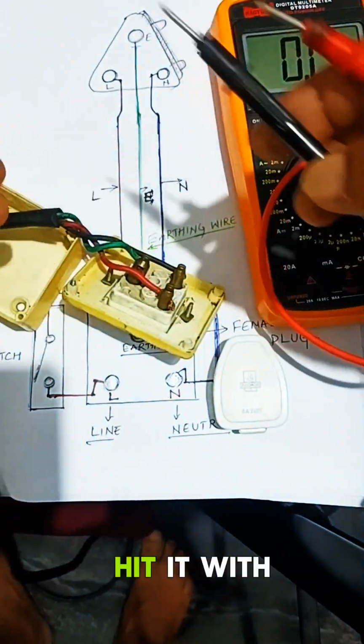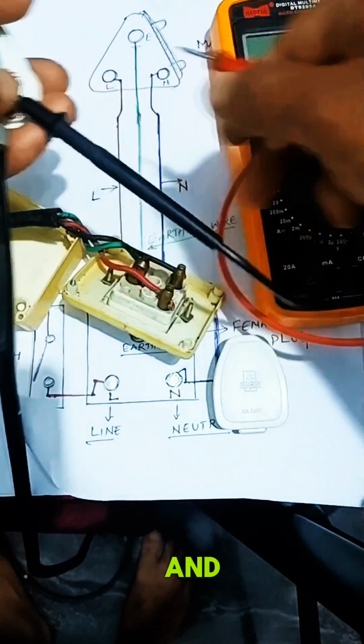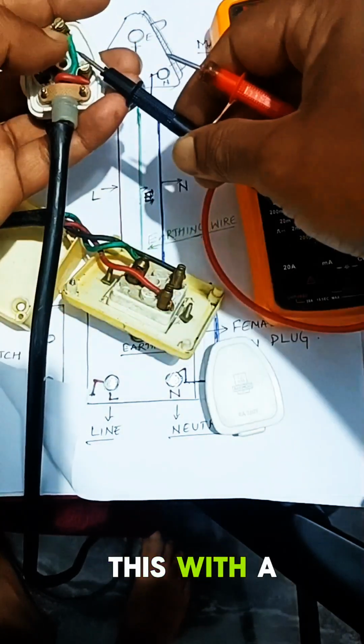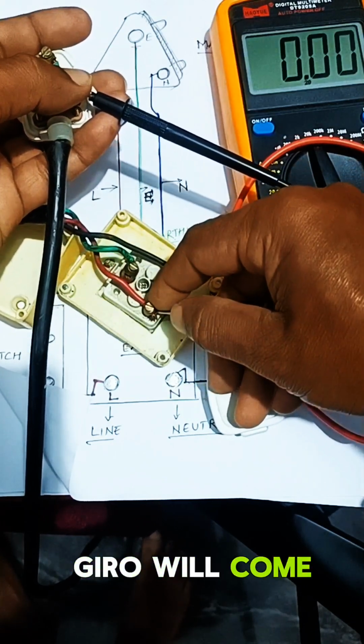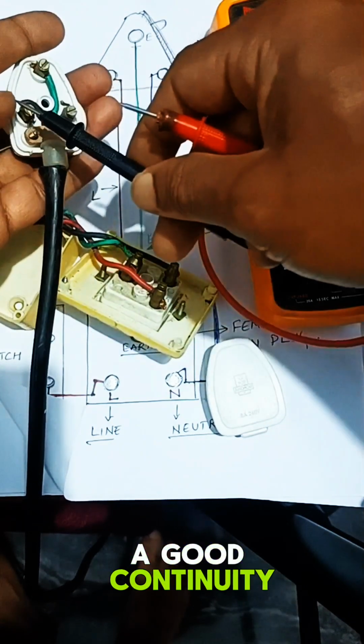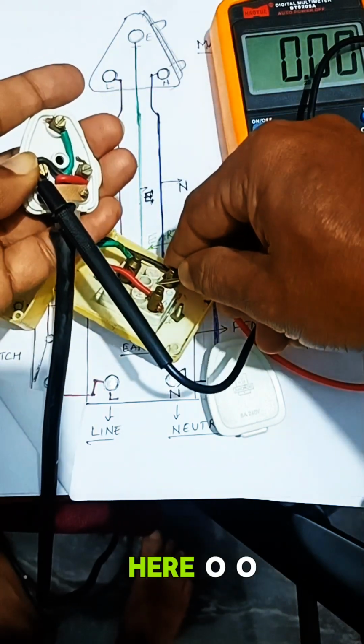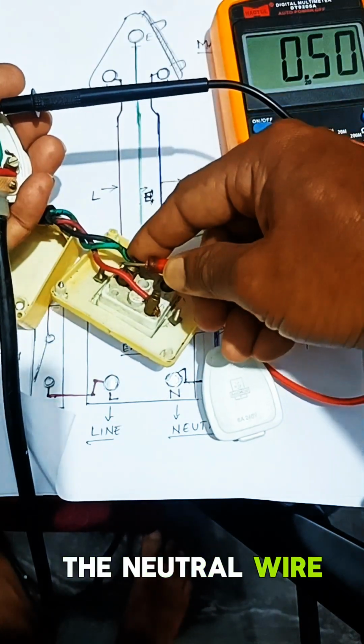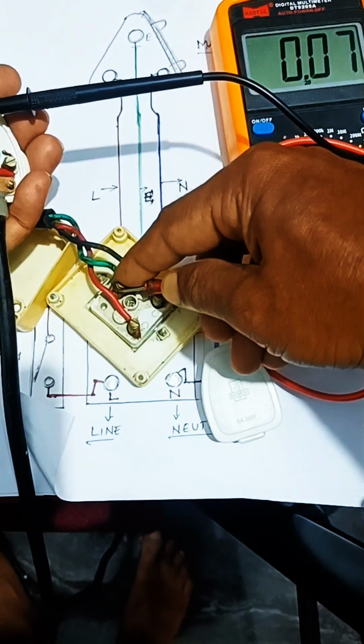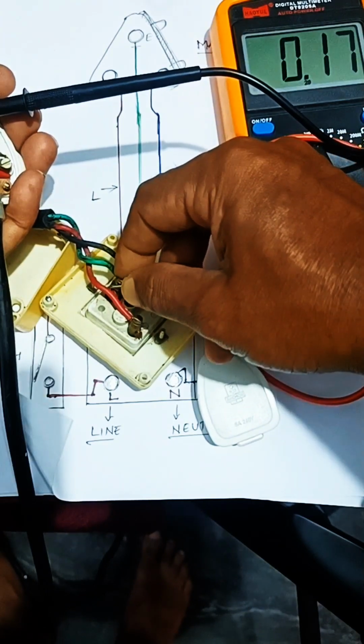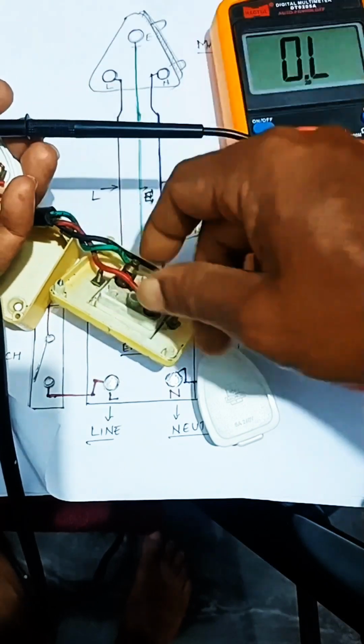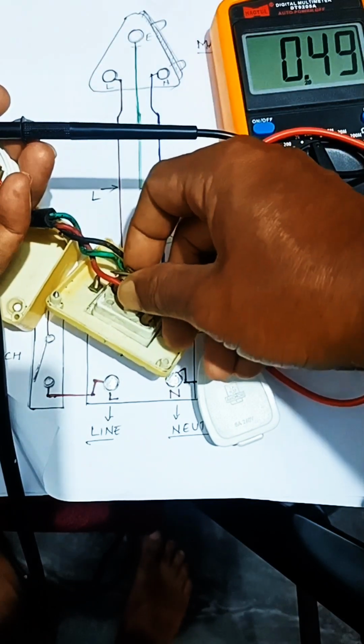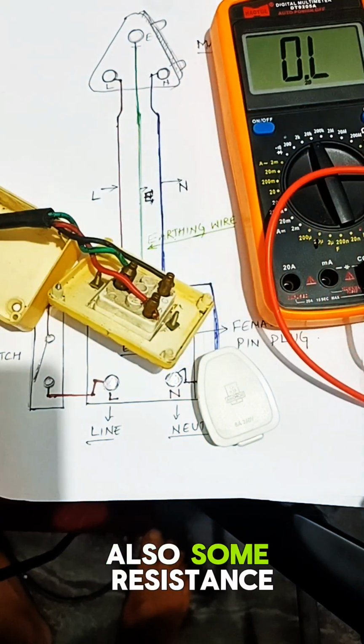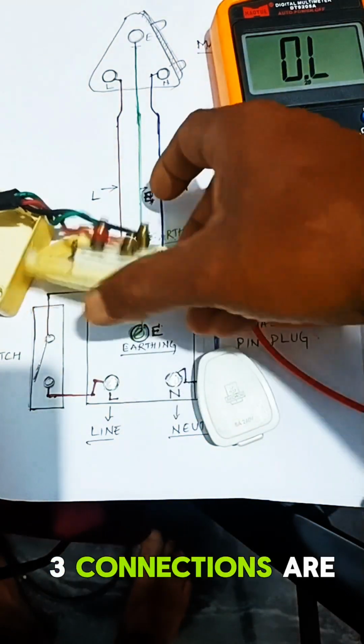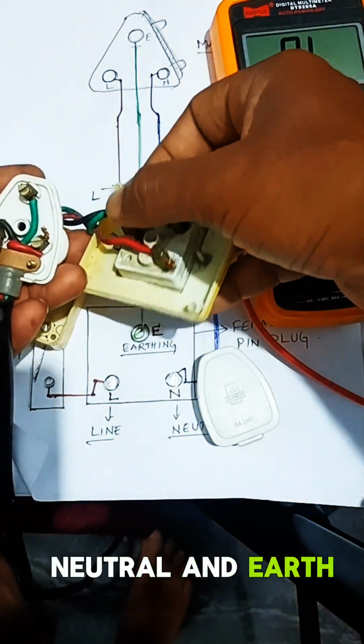Same thing you can check here, with the line wire. I kept one probe on the line wire and this on the line wire of the male plug. Here 00 will come. It shows that the wire has good continuity. Same thing with neutral. You can check here, 00. So continuity is okay. Now with the neutral wire and earthing wire. Here also. So there is proper earthing also. Some resistance is showing because some rust has occurred here, but all three connections are okay: your line, neutral and earthing. So this is how you can check the extension wiring and repair the extension using a multimeter.